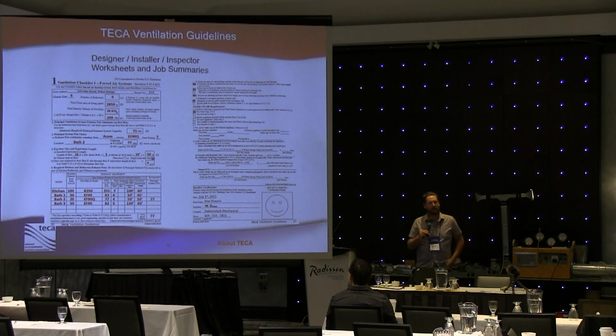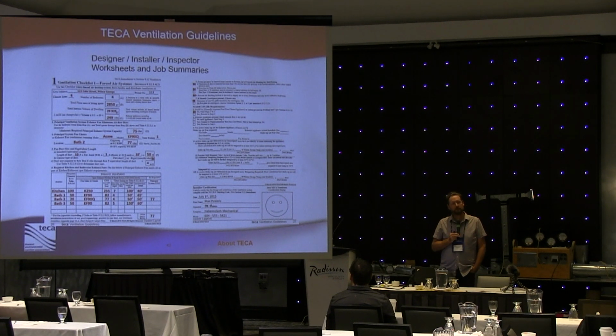Have you guys ever thought, because your checklists are for forced air, HRV, recirculated, and passive, have you guys thought about doing a separate checklist for renovation where the HVAC system may not be being touched, but it's a full kitchen remodel? So we sometimes see that, and we'll usually, if it's a large increase in the CFM of the fan, ask for the checklist, but there isn't necessarily a specific one. When we get back, we're not touching the HVAC systems, and we're looking for confirmation of whether or not we need makeup air, because you've got the naturally aspirated lines that you're increasing that fan. So I don't know if you guys can examine doing this separate.